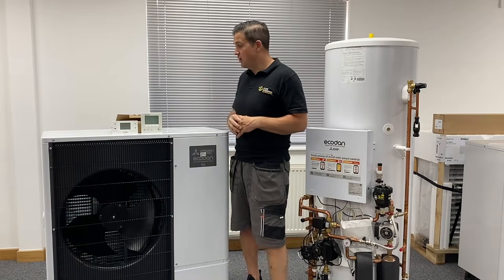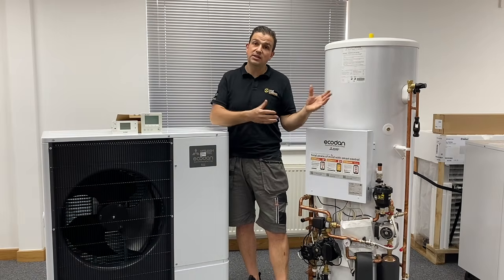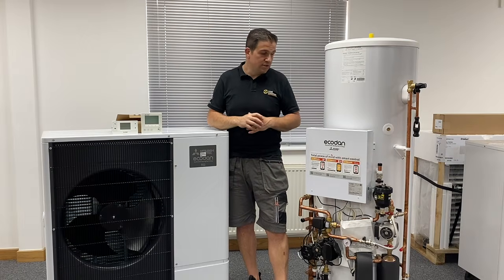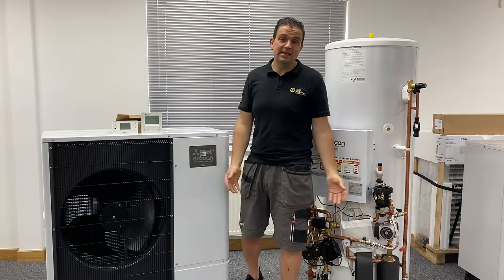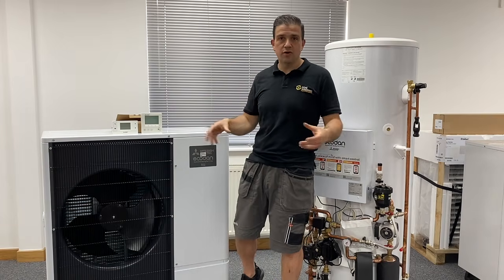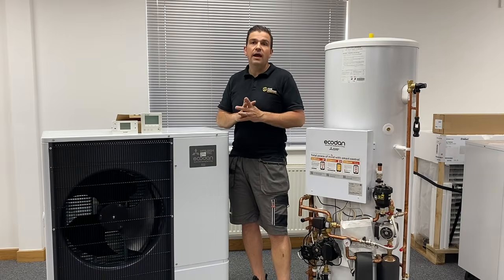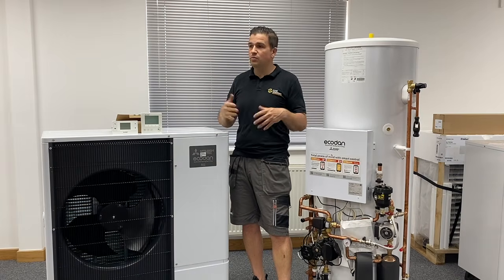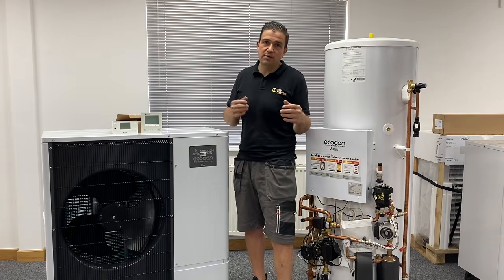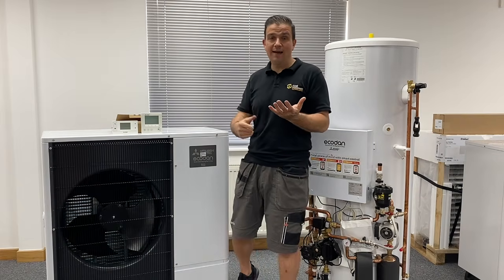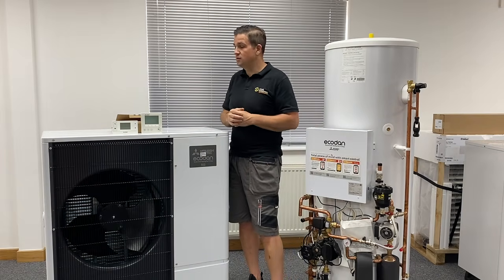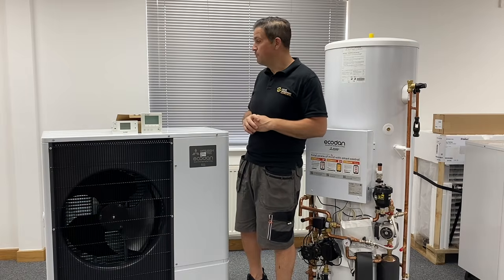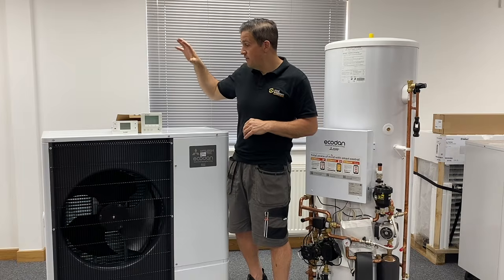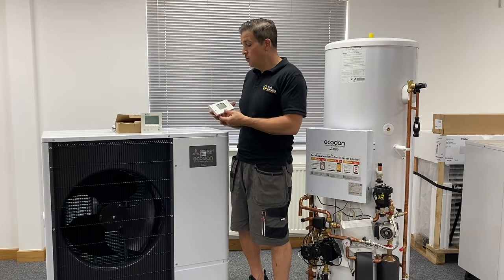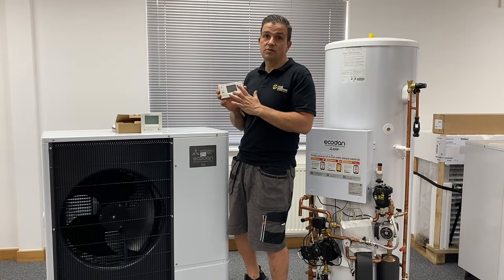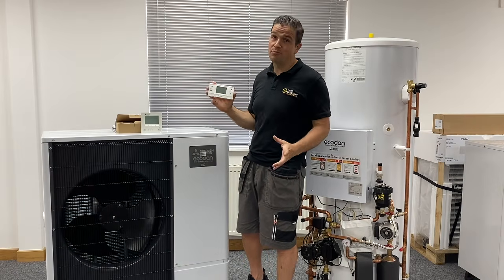We would then typically, in the case of the installation that we're putting the Ecodan in that I mentioned earlier, what we'll end up doing, we're going to have underfloor heating downstairs. So that's going to be zoned, and it will have its own control. Each room will have its own control, and that will be a third-party control. We'll be using a Heatmiser, for instance, a wireless Heatmiser that has the capabilities of getting onto apps, etc. So you can use it via your mobile phones, or laptop, tablets, whatever. Then, if we've got a radiator system, which we will have, we'll use one of the Mitsubishi wireless controllers. Now, very, very simple to use.